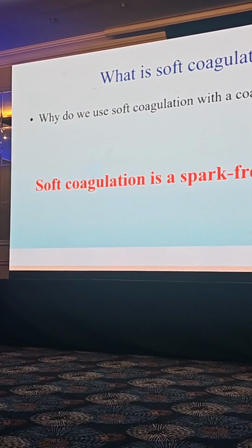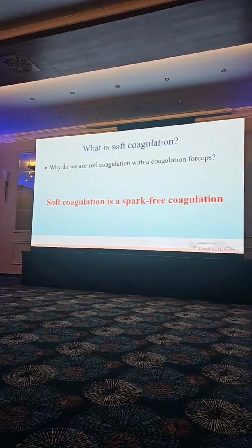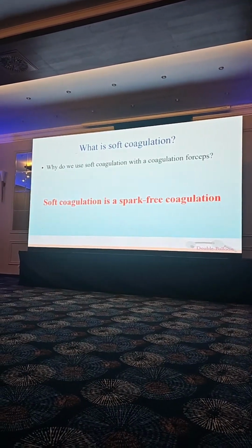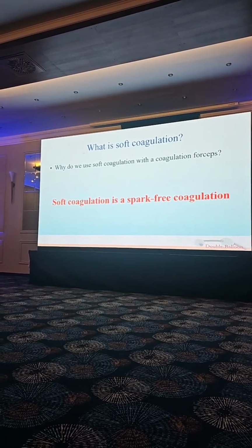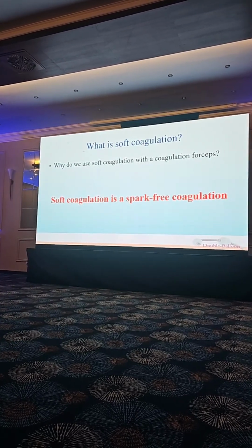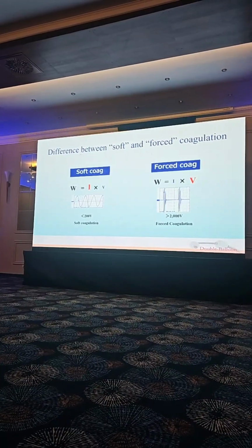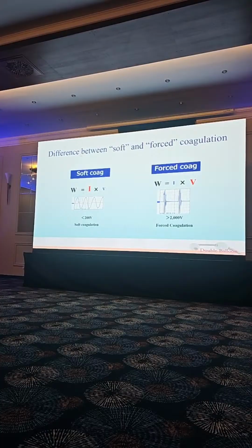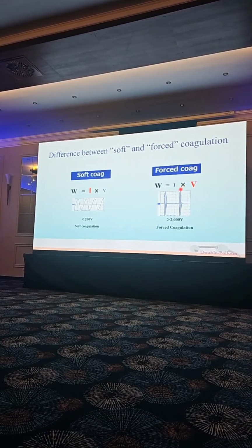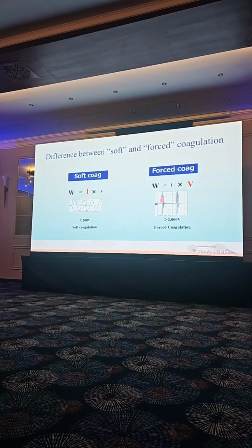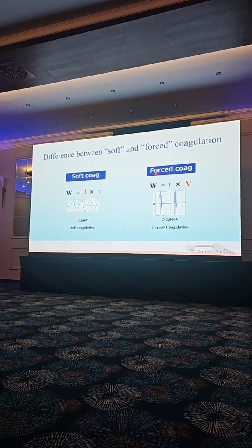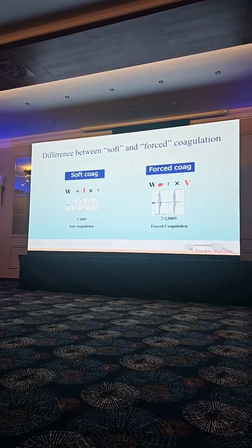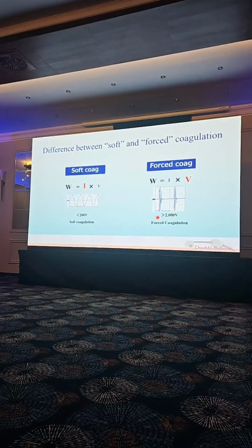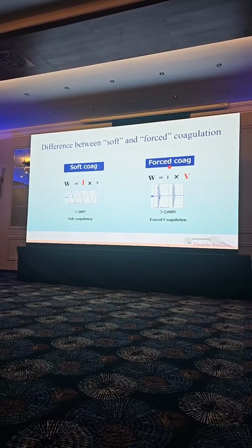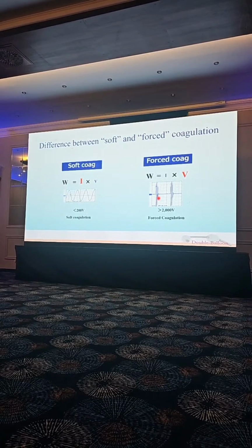What is soft coagulation? Why do we use soft coagulation for the coagulation forceps? That's because soft coagulation is a spark-free coagulation. We don't want to destroy the vessel wall during the hemostasis. That's the reason why we use soft coagulation. Soft coagulation is a very special coagulation mode. Usual coagulation mode, like forced coagulation, has a high voltage, but the power is limited by limiting the current. So the voltage will be as high as 2,000 volts, but current is limited. So in that way, we can eliminate cutting.